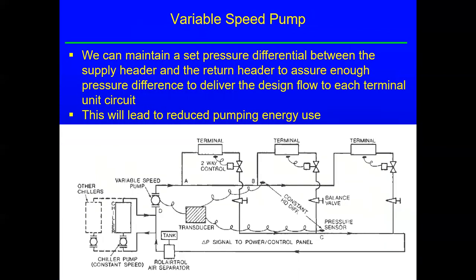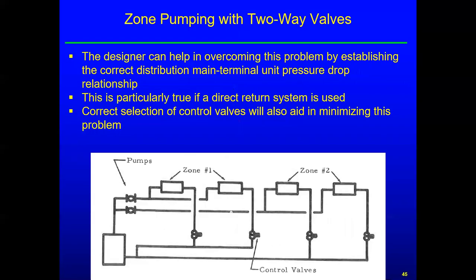Okay, and so this is illustrating more on the variable speed pump. So we can see that we have a pressure transducer at B and a pressure transducer at C. And the B is at the supply header and the C is at the return. And so we simply have a set point to maintain whatever differential pressure we need to force flow through the terminal units. And we maintain that by modulating the pump speed. So that works very, very nicely. So that would be a recommended condition. And it works well, and it reduces pump energy. So that's pretty good.